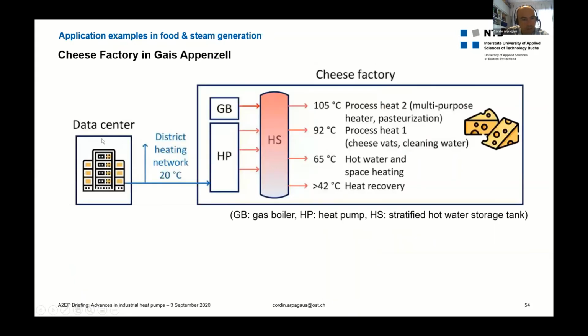So it's shown here: we have the data center, the district network, the heat pump, and a hot storage tank, serving different processes in the factory. With the heat pump, space heating can be provided, as well as hot water and process heat. There is a gas boiler as redundancy and to cover peak loads for process heat at 105 degrees—a good example where a heat pump and a gas boiler are combined.